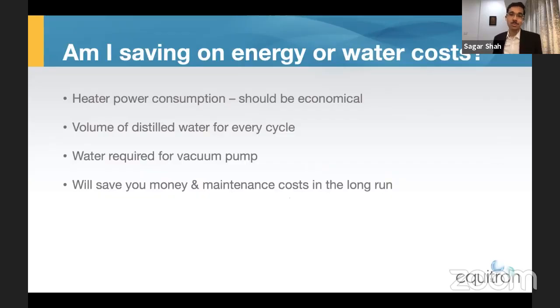Now, this is a point that is often ignored, energy and water savings. But undoubtedly in today's world, it is vital that we give it the attention that it rightly deserves. When most laboratories make a decision on an autoclave, energy savings in the long run is a point that is overlooked by most. Most autoclaves, in fact, have pretty high power consumption and may also consume tremendous amounts of water. Modern autoclave options do enable you to cut down these electrical costs to anywhere between 20 to 40%, but you still need to check with your manufacturer of the autoclave about the water requirement for every cycle and how much water is going to be consumed at the end of every cycle, because there are special accessories and steps that could be taken in order to reduce the water consumption.